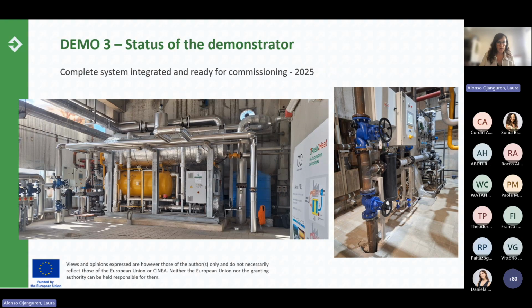And this is how the whole system looks when installed into the plant. So we have the EHT. At the left side, we can see the steam generation module, only a small part can be seen here. And here are the pumps for the waste heat that comes into the system. Here in the right picture, we can see the steam generation module a little bit closer.